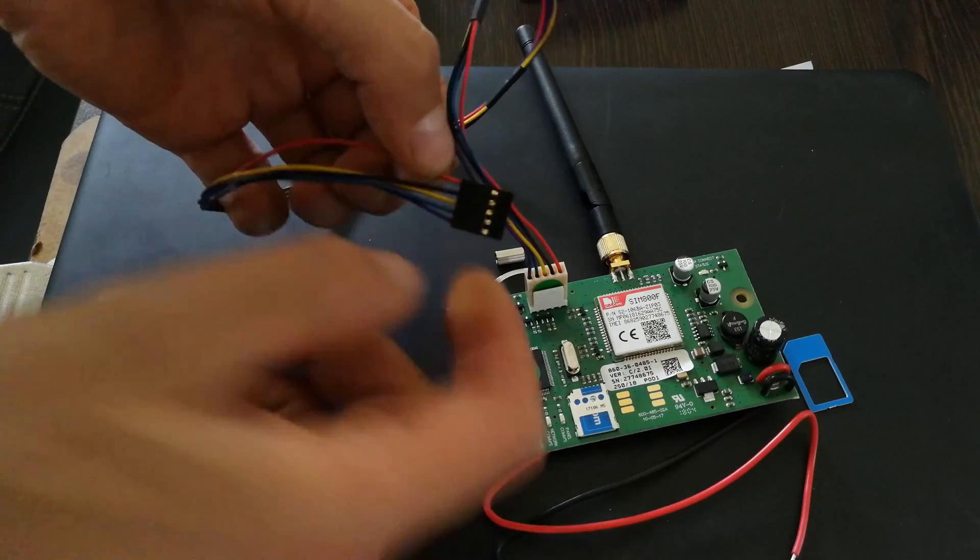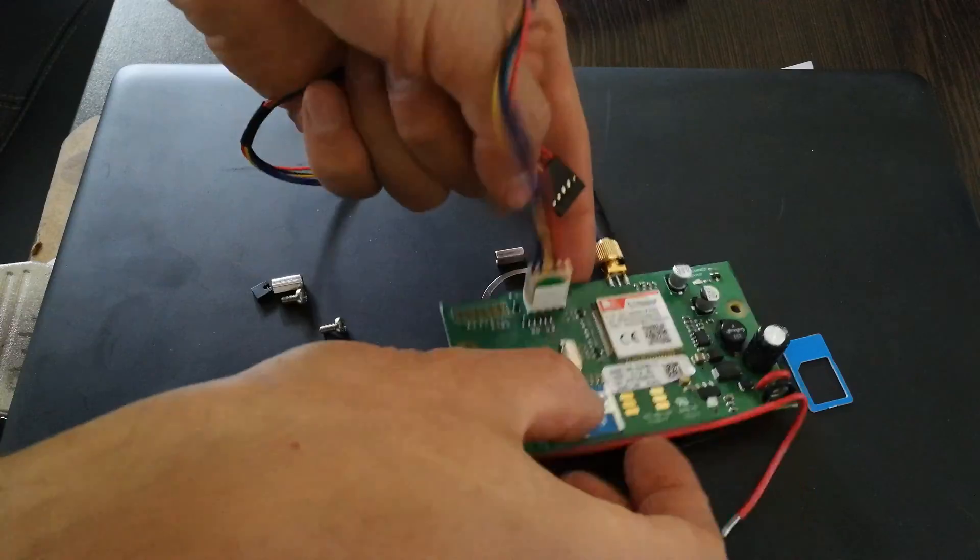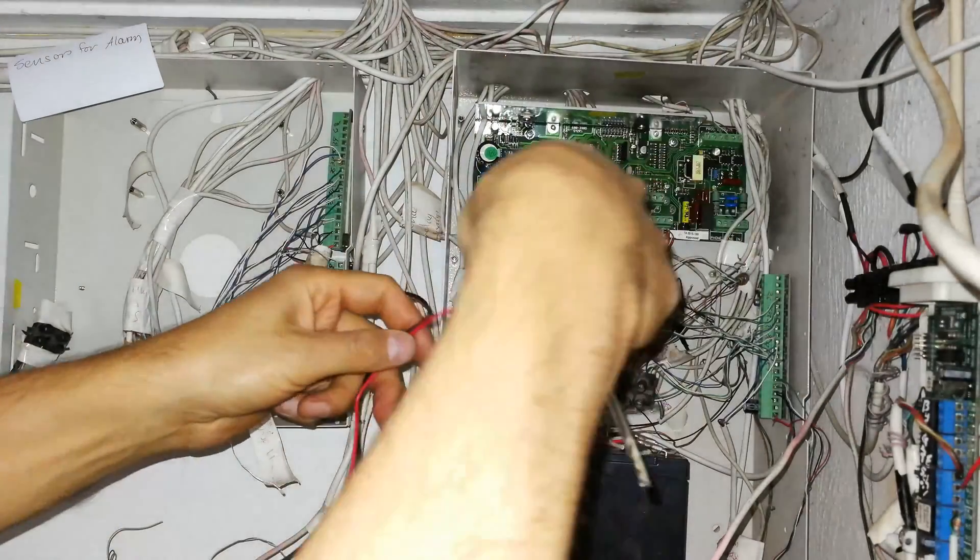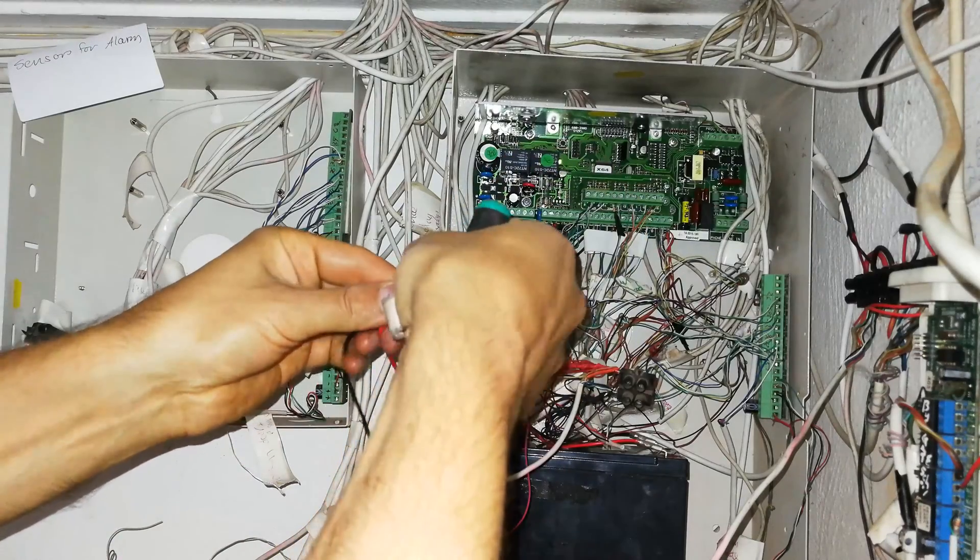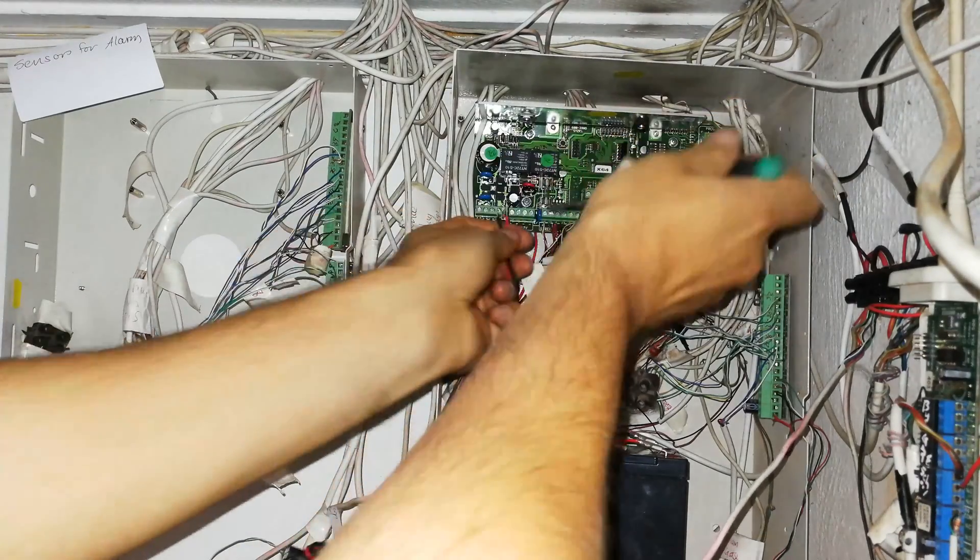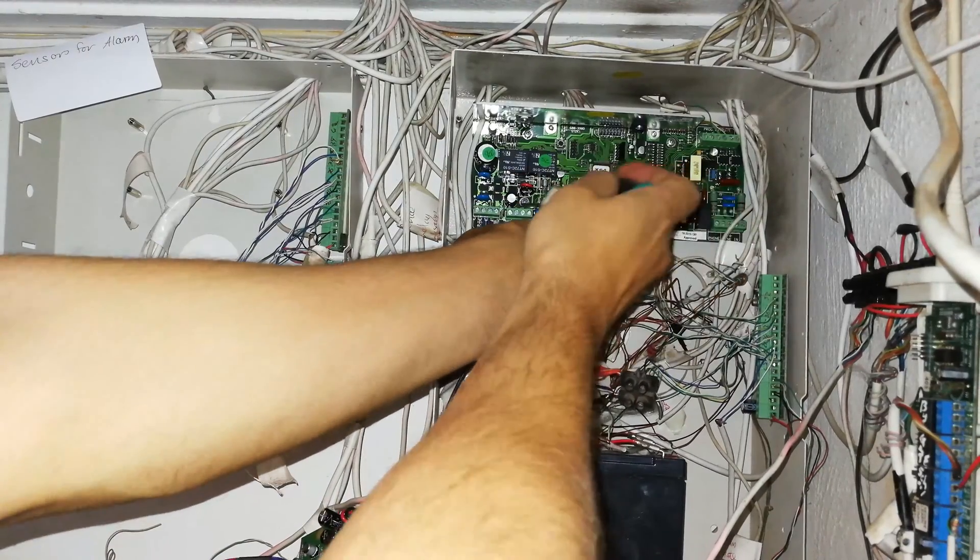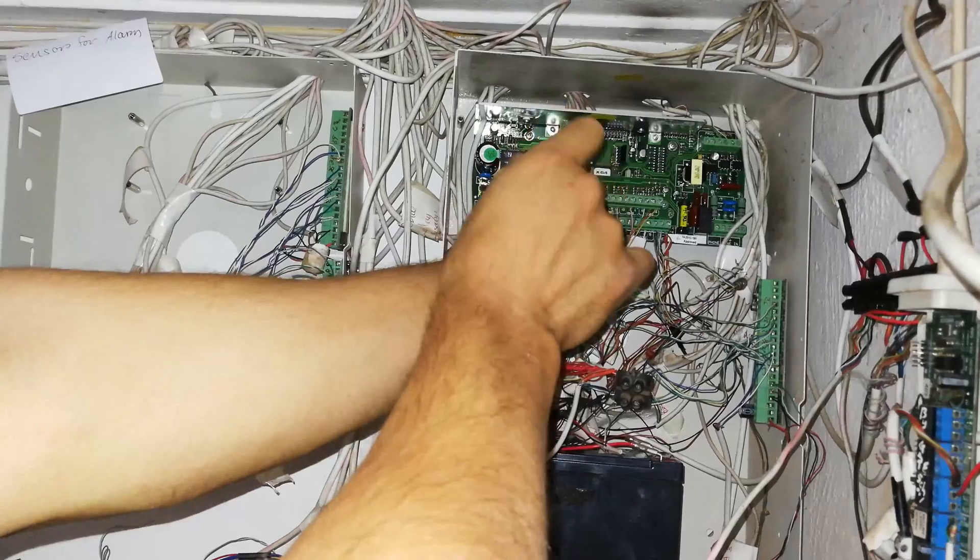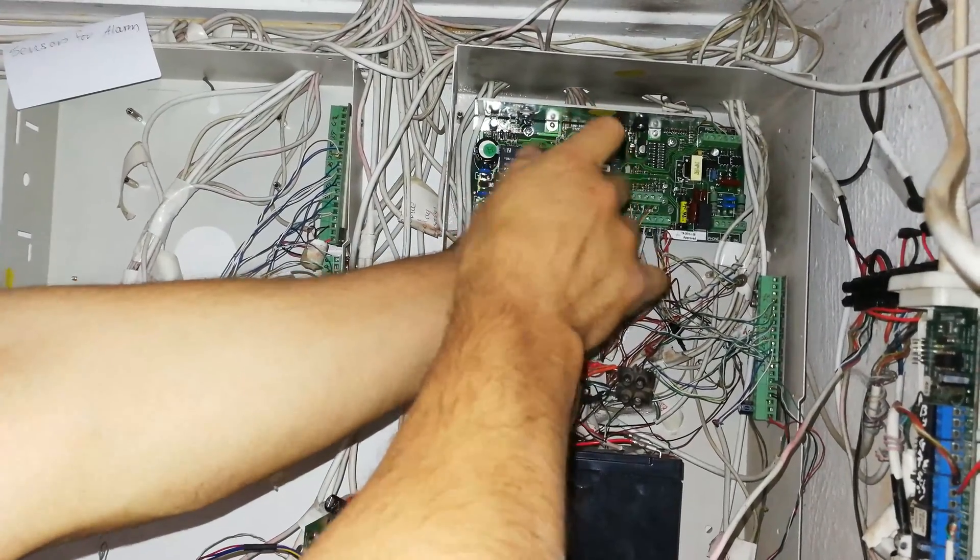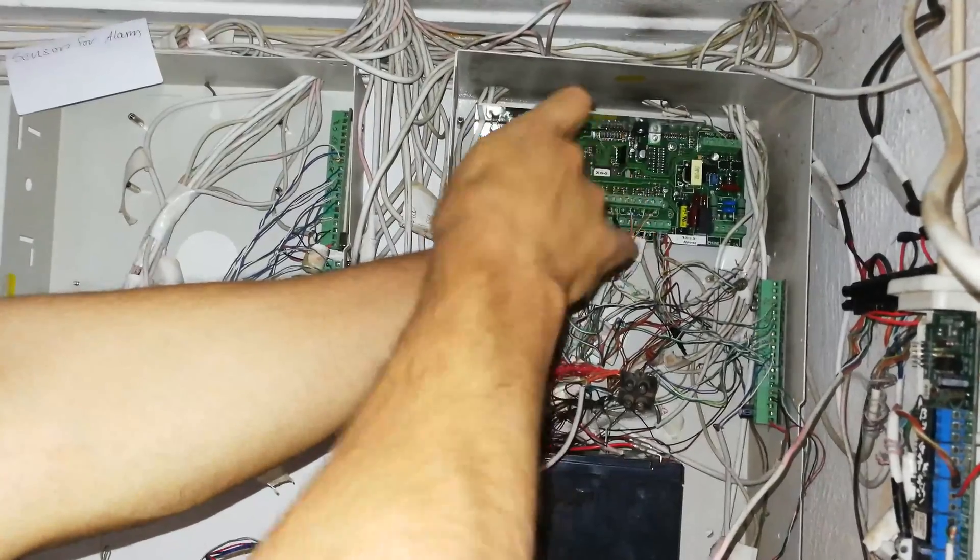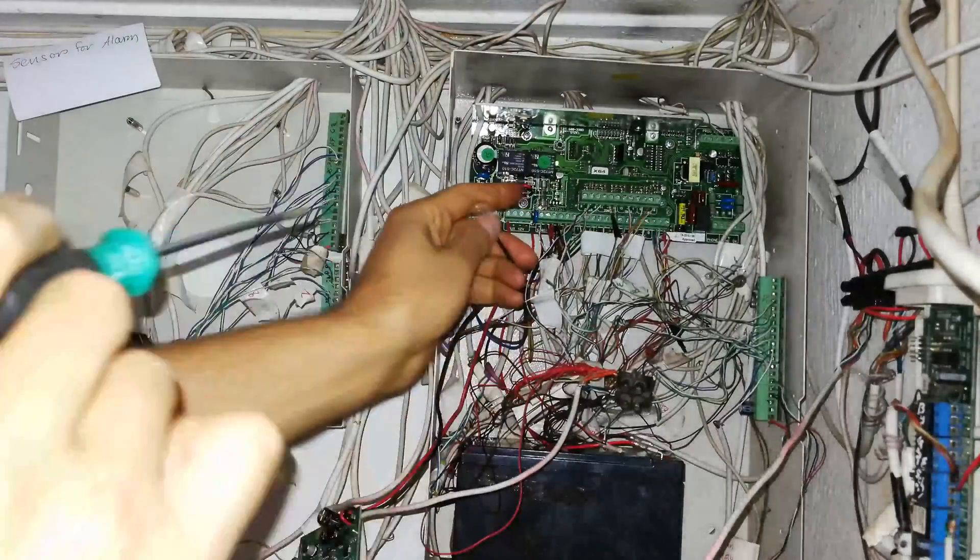As you can see, this side's got to go to the panel. The red cable goes to the top, and I'll show you when we're at the panel. The procedure is to first power it up, so you want to connect the positive and the negative to the auxiliary. Make sure that if you are using this X-series communicator, you power it up from the panel, because if you don't get the power from the panel, in my experience it pops the serial port—it pops the serial chip on the board.